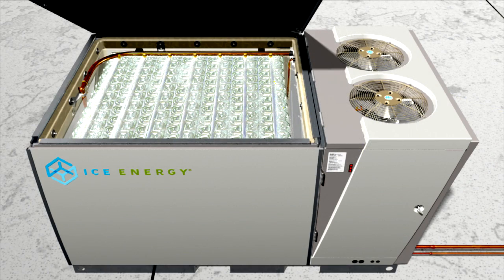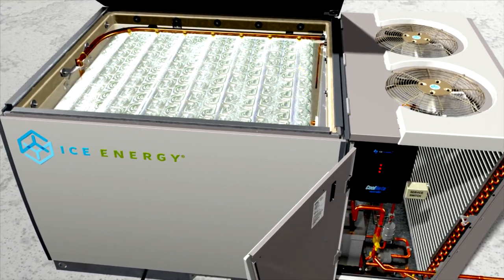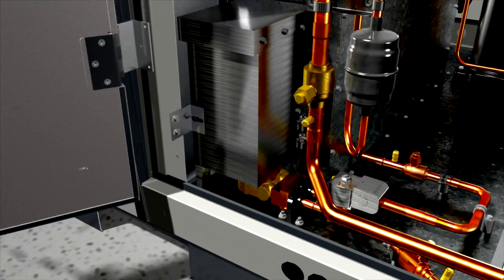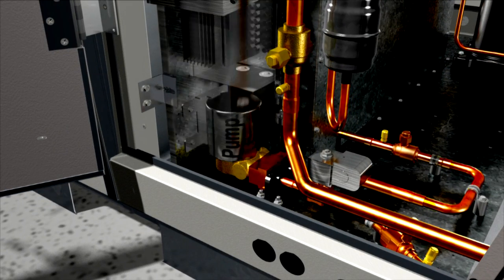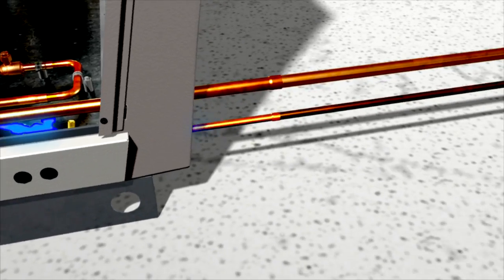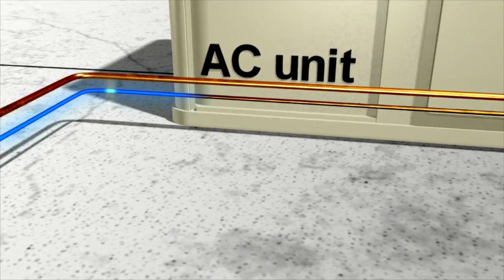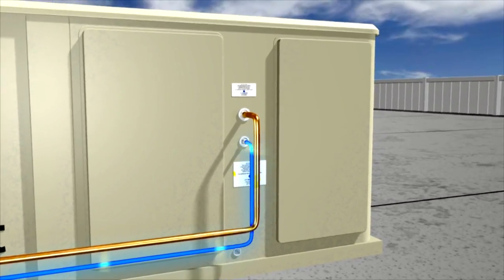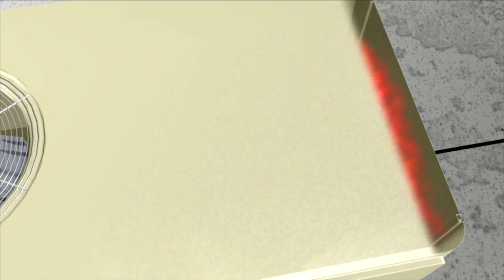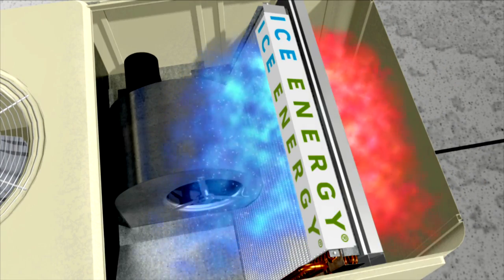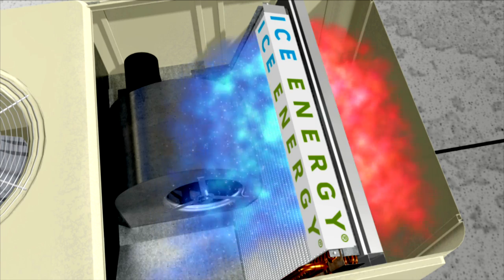The IceBear unit, fully charged from the night before, switches to cooling mode. A small, highly efficient pump pushes ice-cold refrigerant through the evaporator coil that was seamlessly added to the building's air conditioner. As warm air from the building is blown across the new coil, the ice-cold refrigerant absorbs its heat.